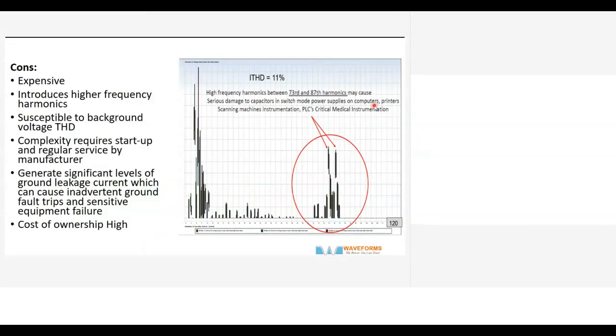They are susceptible to background voltage changes. If there is higher distortion, it may not be effective. Then the complexity requires startup and regular service by the manufacturers. So it needs regular service and maintenance, so the cost of maintenance goes up. Generally, there are significant levels of ground leakage current, which can cause inadvertent ground fault trips and sensitive equipment failure. That can be a common mode noise which can cause disturbance in electronic systems. The earth neutral voltage can go up and it can cause other issues.